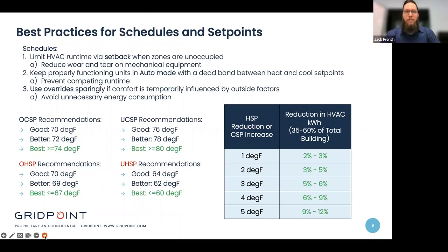Great. So how do we address some of those challenges? We'll start off with best practices, and best practices for schedules can include some of the following points. Number one, limit the runtime of your HVAC units via setback, especially when zones are unoccupied. This helps you by reducing your energy consumption, also helps you by reducing the wear and tear on mechanical equipment, and it increases the lifespan of your units. Second would be keep properly functioning units in auto mode with a dead band between heat and cool set points. Auto mode will allow the units to switch between heat and cool call when they need to, and the dead band helps to reduce competing runtime.